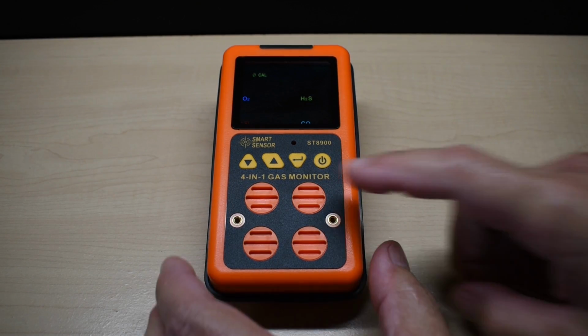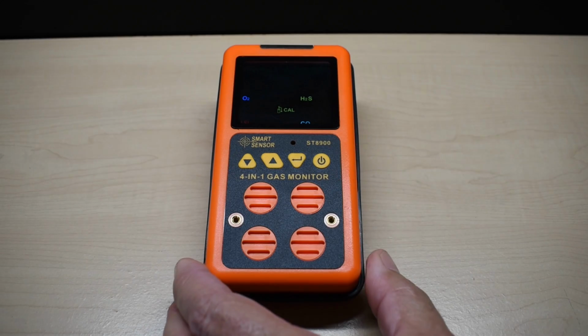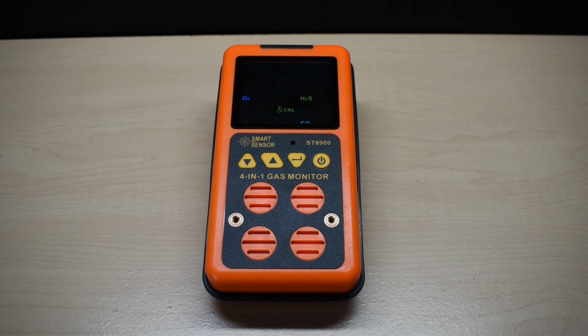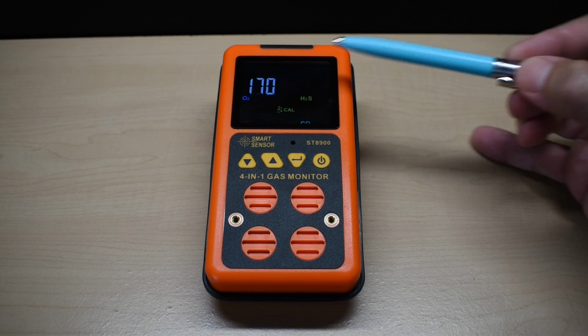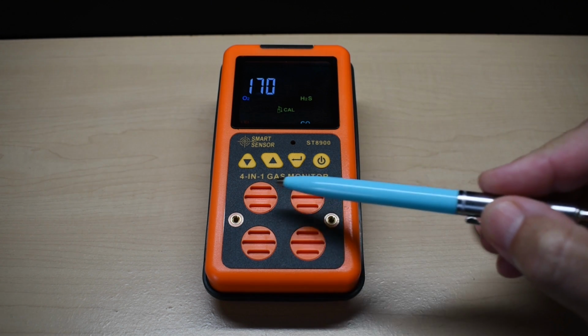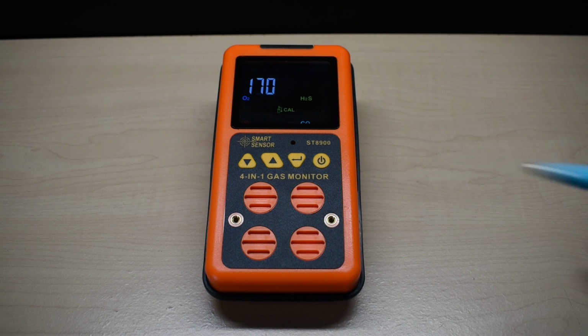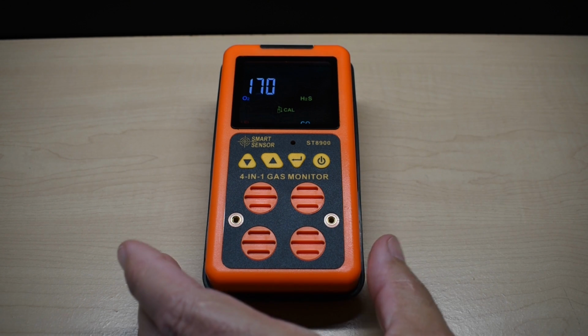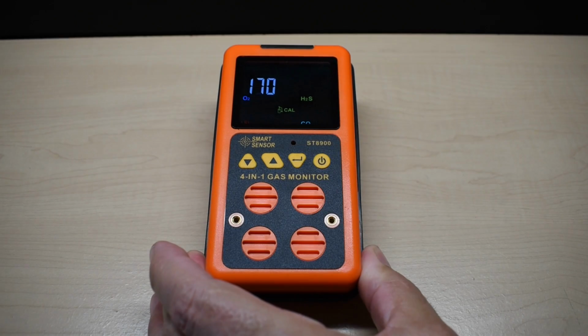Okay, I'm going to push it one more time. It says calibrating. Enter. And right now it's calibrating the oxygen sensor, and I believe it's this one right over here. This is going to correct any issue you may have with this unit if you get it and the oxygen alarm is triggering. That's pretty good, so hit enter.